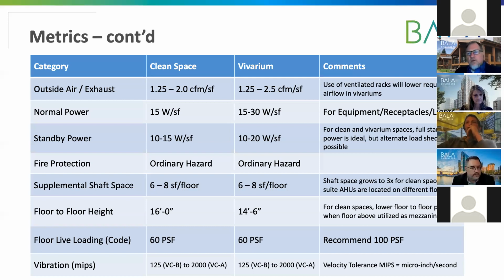Steve, Scott, we have a question on the height of the clean room. What would be the clear height of the inside of the clean room if you had a 16-foot floor to floor? Typical would be about 9 foot at that level. And it's an excellent point. All the values we've given are based on a 9-foot ceiling for Vivarium, clean space, and lab. So obviously, if you're able to drop your ceiling heights, that's another way to work that in, because we have actually done that on a couple of projects where we might be looking at 8-foot ceilings in order to get some of these to work, where we have less than the 14.5.